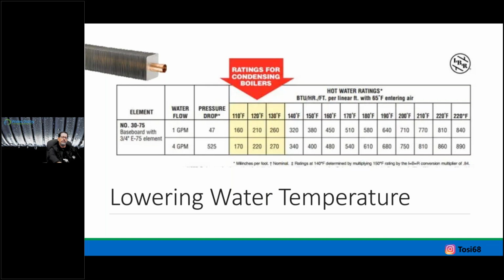I need 2,000 BTUs in 1 out of 6 rooms of this zone. If one room is grossly oversized, I can only imagine all the other ones are as well. So let's just take a cast iron boiler with baseboard, 140. That now delivers 320 BTUs per every foot of baseboard. That room with 10 feet, that's 3,200 BTUs. I only need 2,000. Again, on a design day. Again, design day of 0, 10, or whatever you want to choose, wherever you live, right?